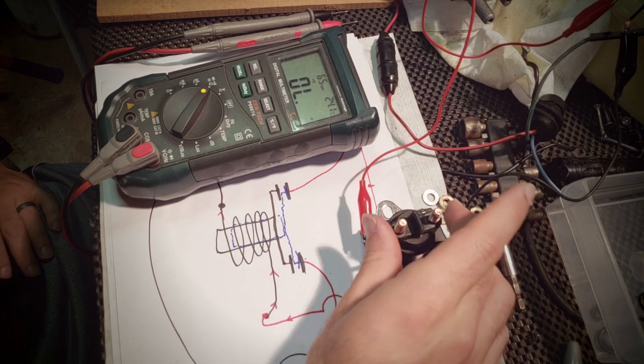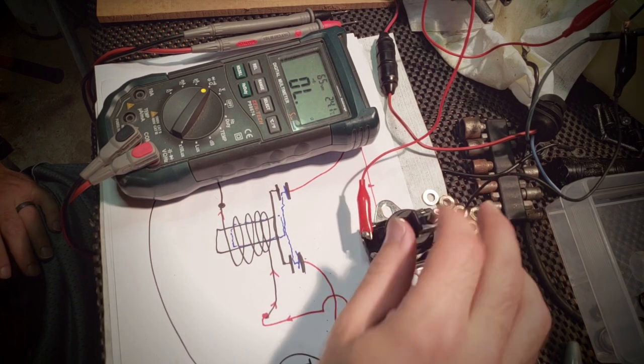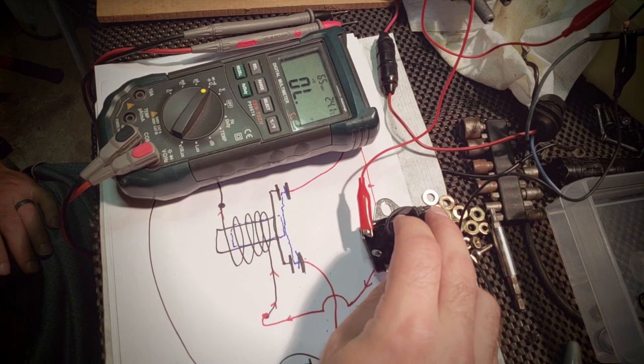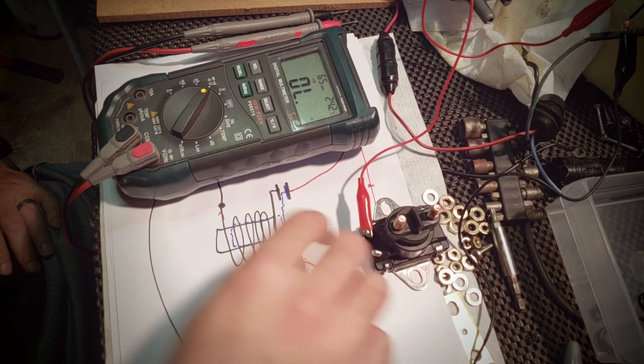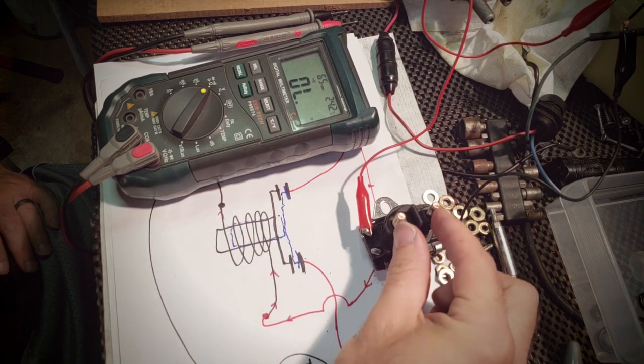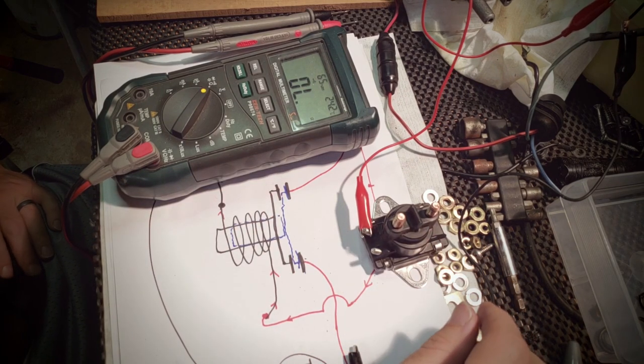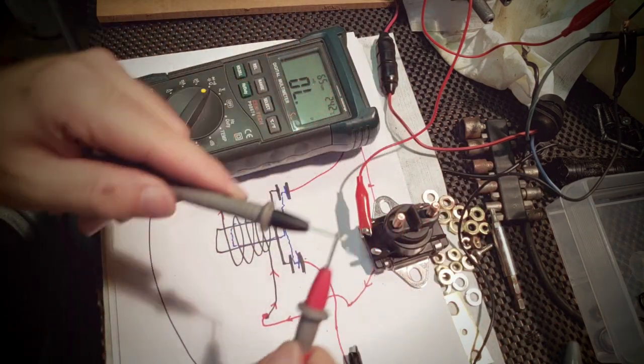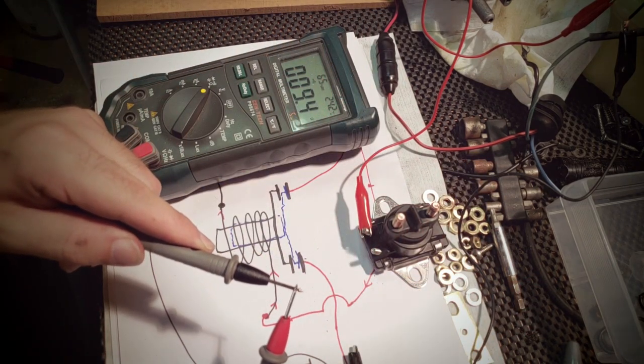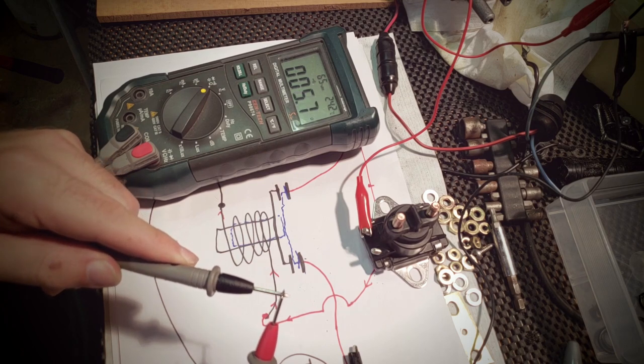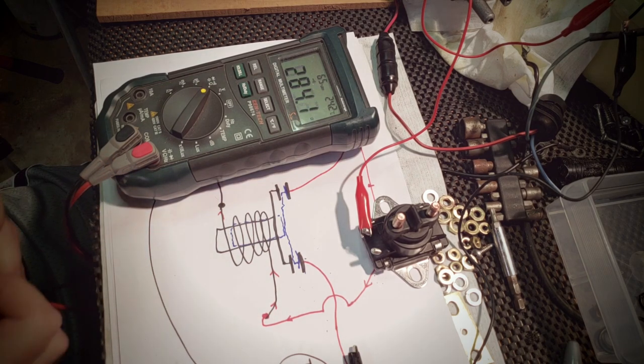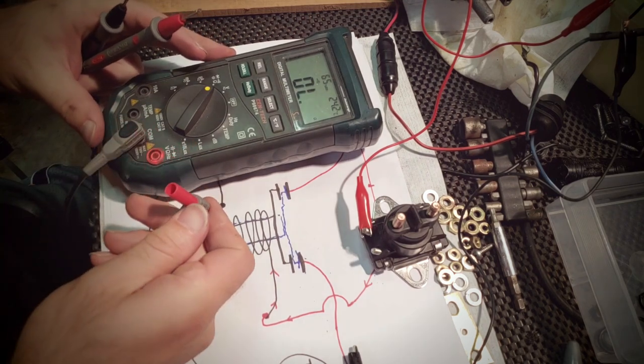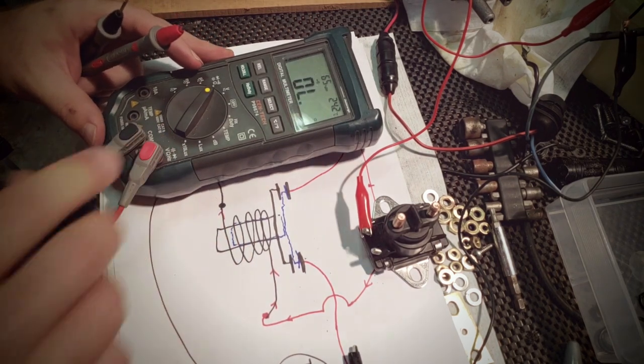Let's go ahead and just for curiosity sake, switch these. Make sure that these are not polarized, which I don't believe is the case. Yeah, still getting a high resistance, about 125 kilo ohms. So what that tells me is this one is not going to work in this particular case. Let's move over to the other one and check it and see if we get the same results. If we do, then I might be a little suspicious that my test is no good, but this should work if the solenoid is good. So let's go back to continuity. Still good there. Got my test leads on the posts.